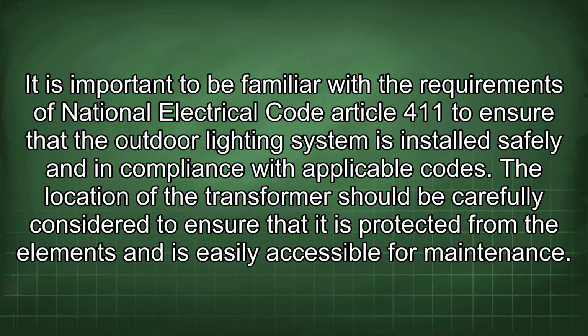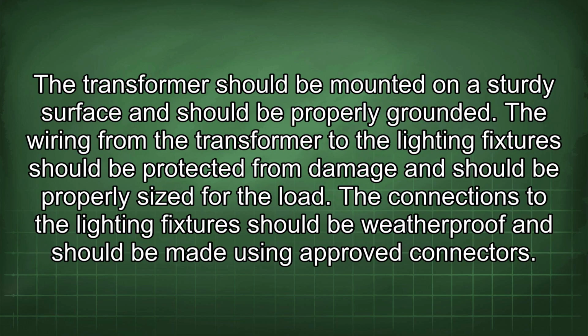The location of the transformer should be carefully considered to ensure that it is protected from the elements and is easily accessible for maintenance. The transformer should be mounted on a sturdy surface and should be properly grounded. The wiring from the transformer to a lighting fixture should be protected from damage and should be properly sized for the load. The connections to the lighting fixtures should be weatherproof and should be made using approved connectors.